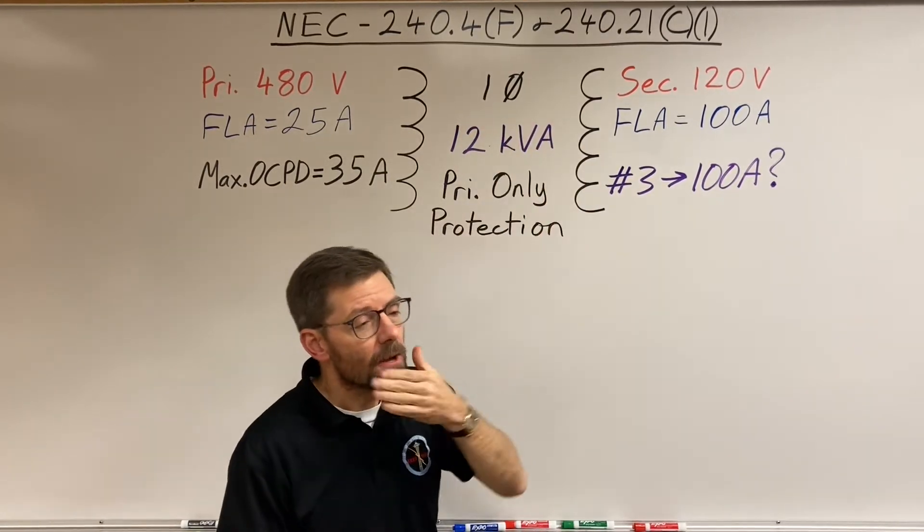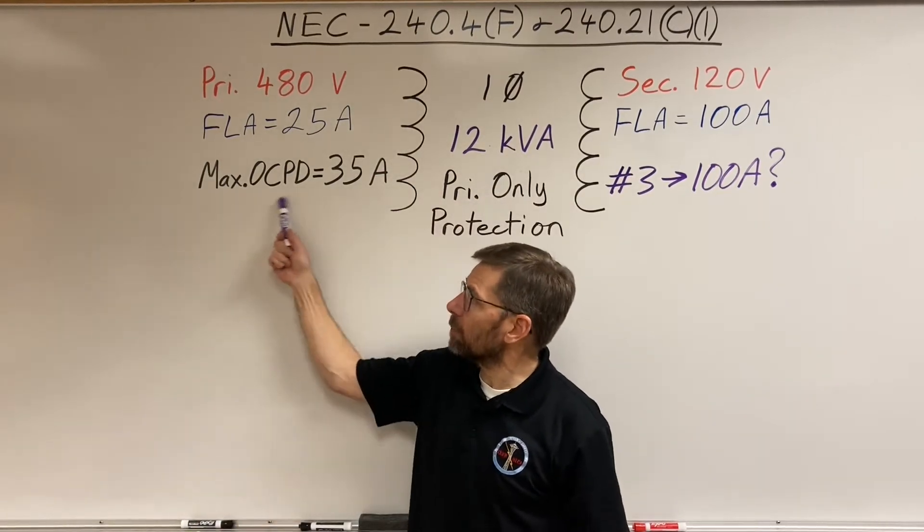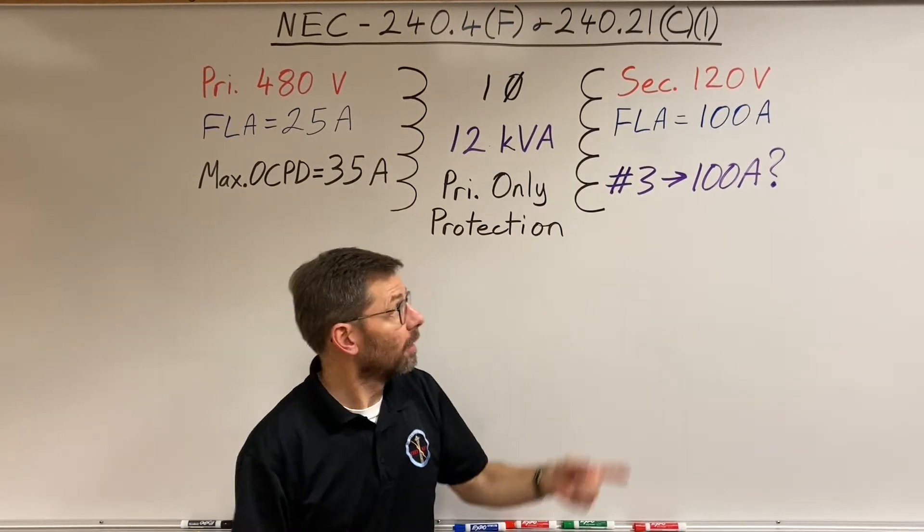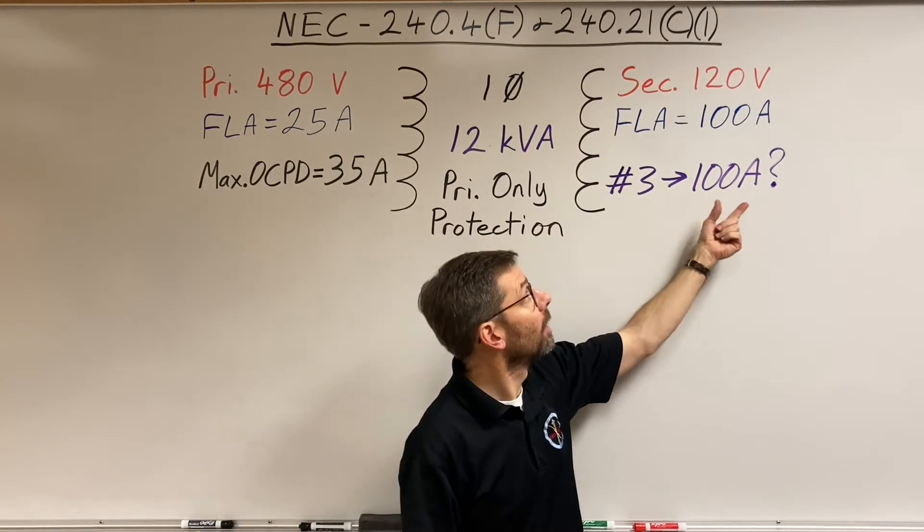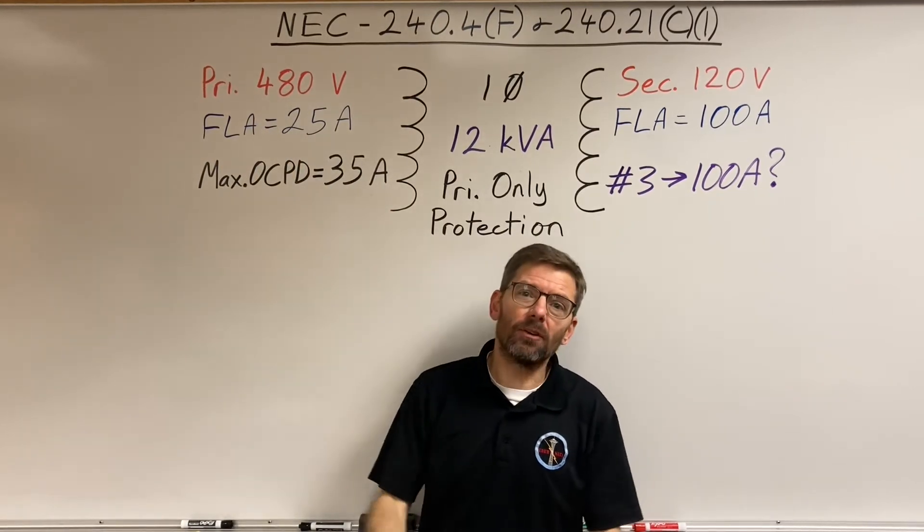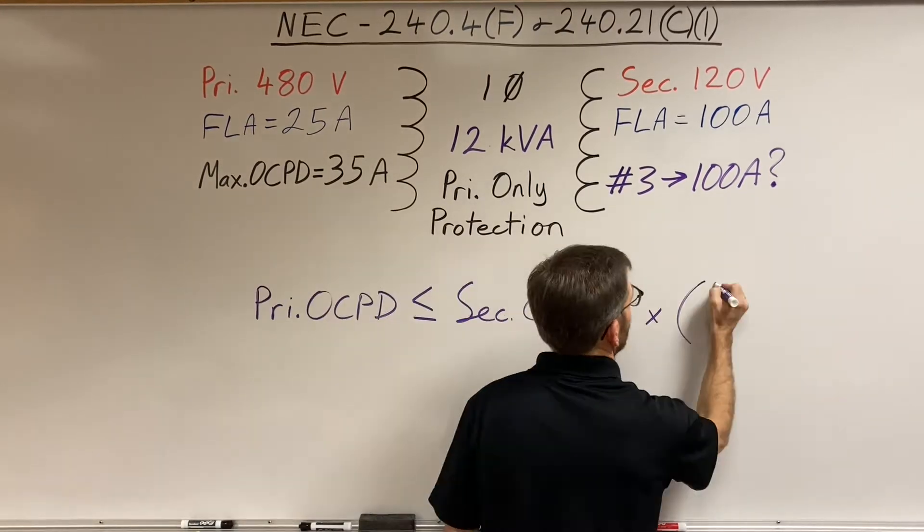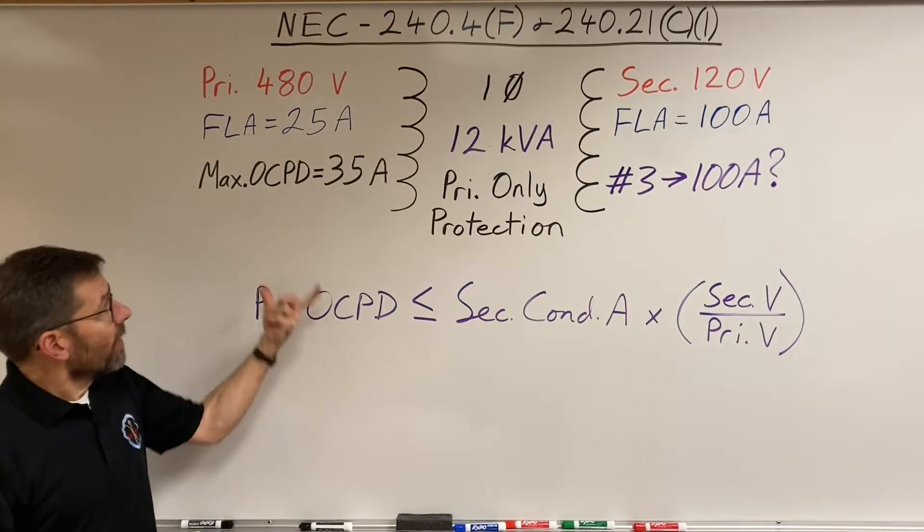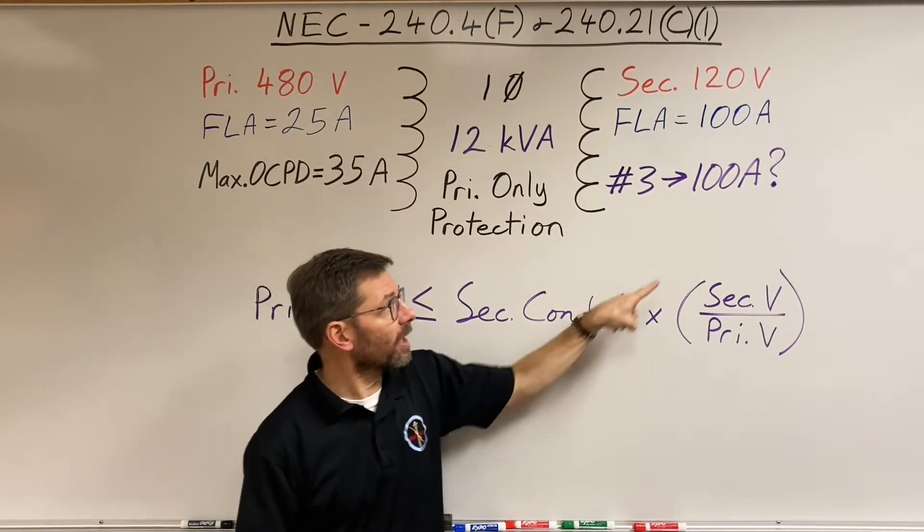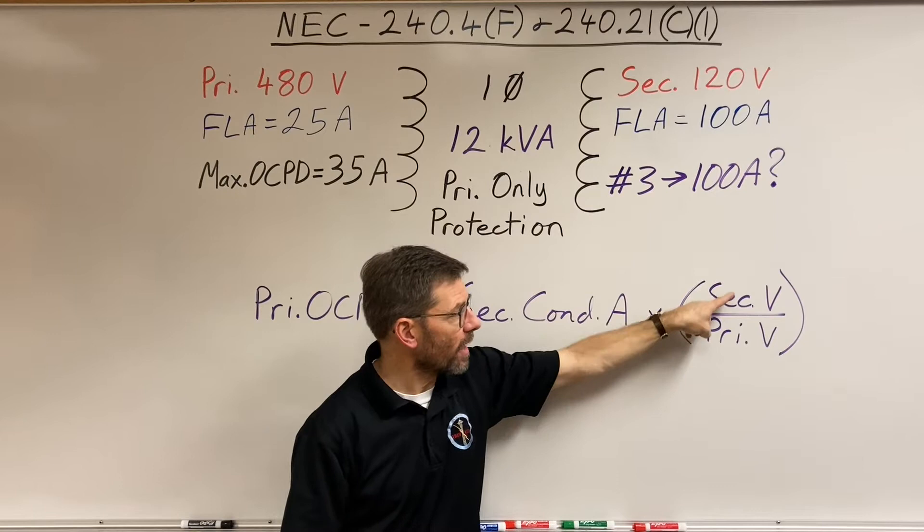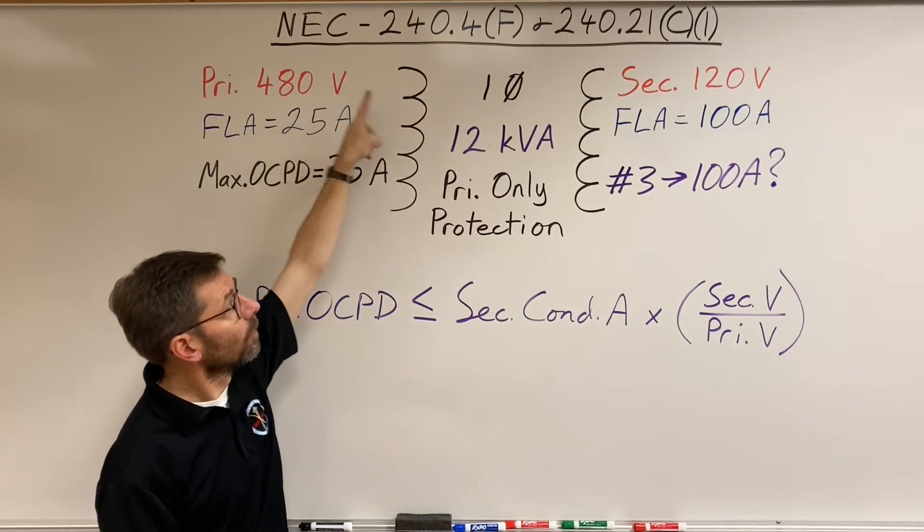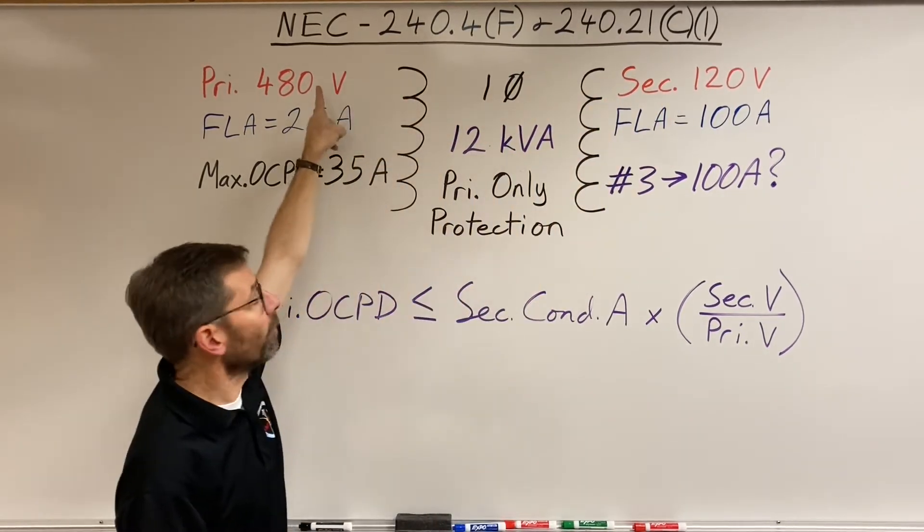Because those two code sections have this language. The overcurrent protective device cannot exceed the value that is determined by multiplying the secondary conductor ampacity by the secondary to primary voltage ratio. That's a mouthful. Let me write it out. The overcurrent protective device has to be less than or equal to the secondary conductor ampacity times the ratio of 120 volts to 480 volts. What is that ratio? 120 over 480 is about a quarter.